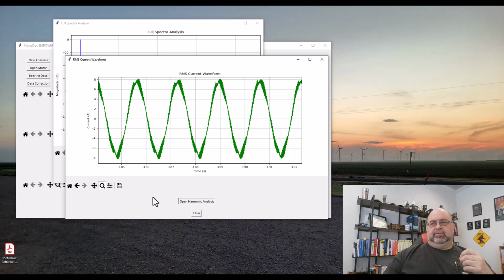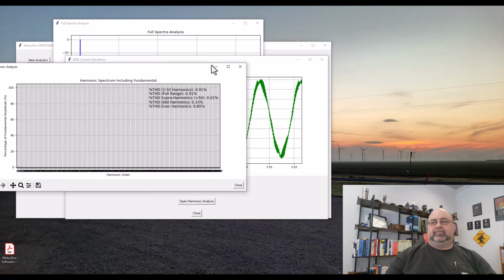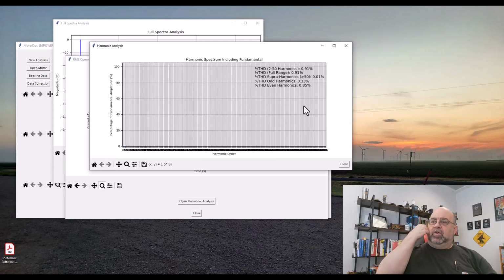What's the reason why? Well, just to shorten up the discussion, they ran a ground lead inside the conduit with 3 loose power leads for about 4 meters, or 12 feet, of basically 3 power leads inducing into the current. So all of this is then transferring to the surface of the machine. With that signature, it's telling me I have very low harmonics and current, which is good. So let's go ahead and close out of these.